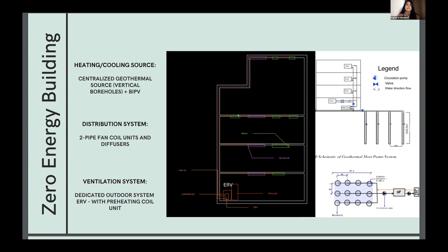Based on our HAP design results, we got the load requirement and airflow rate for each room, system, and unit. As seen in the diagram, the load for each mid unit required 3.7 tons, and each corner unit required 4 tons.